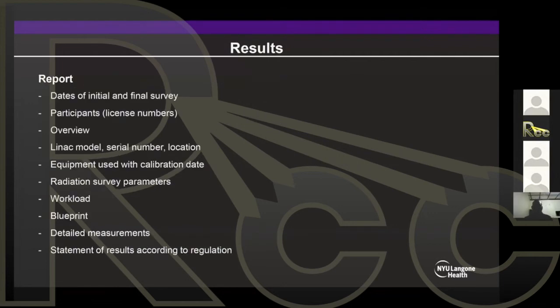Okay, so let's move to what is in your report. At the end of your survey, you're going to have a report with the dates of the initial and final surveys, participants, an overview, Linac model, serial number, equipment that you used with the calibration date of each of your radiation meters, the radiation survey parameters. You're going to have your workload, a blueprint with the areas that you surveyed, your detailed measurements, and also a statement of results according to regulation. So, as a conclusion, with this measurement we can justify we're meeting all the regulatory limits.